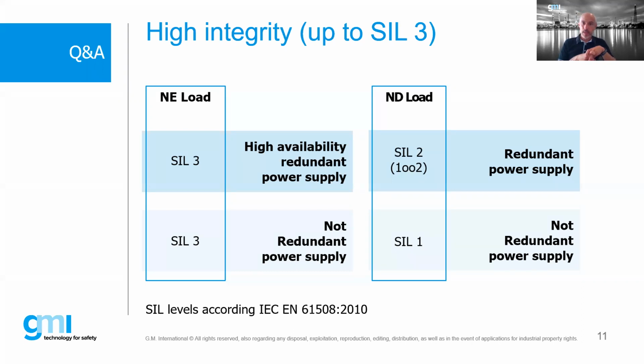over. The difference in normal de-energized load is quite important, because for fire and gas, for instance, you use just one safety power supply, because the SIL you reach, if you use a safety power supply, not a standard power supply without FMEDA calculation, with one, you reach the SIL 1 level, no redundancy. If you use two redundant power supplies, you reach a SIL 2.